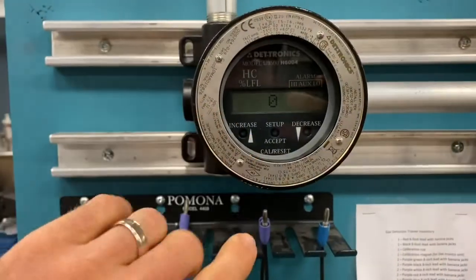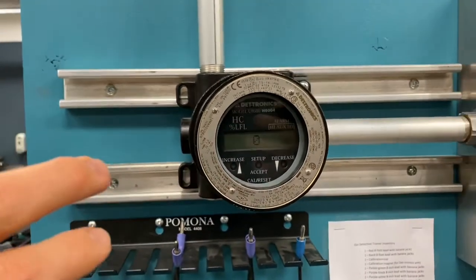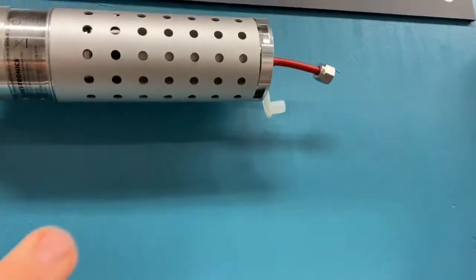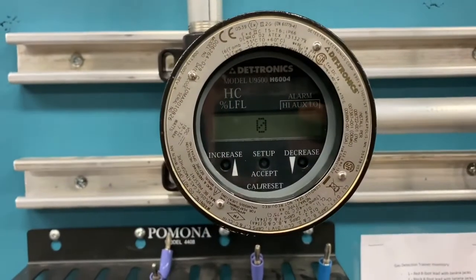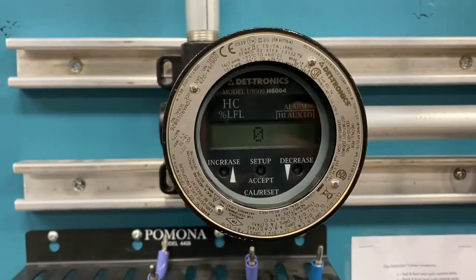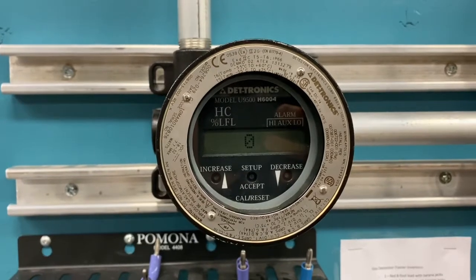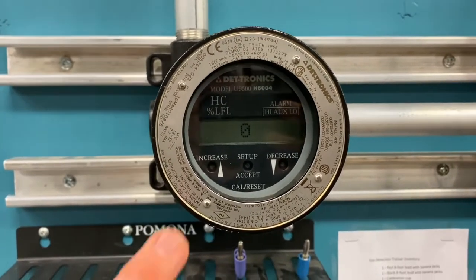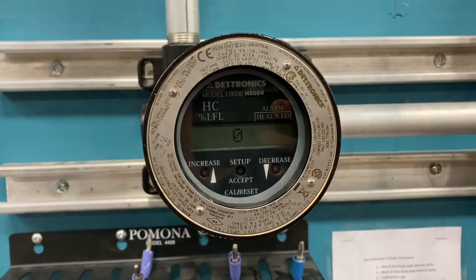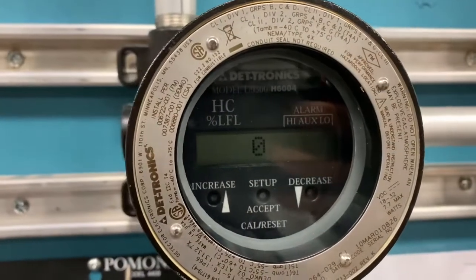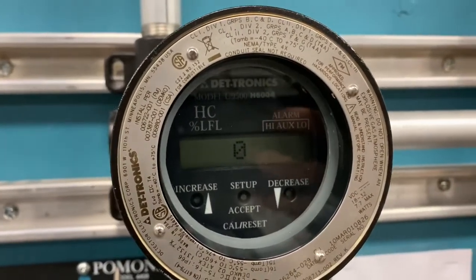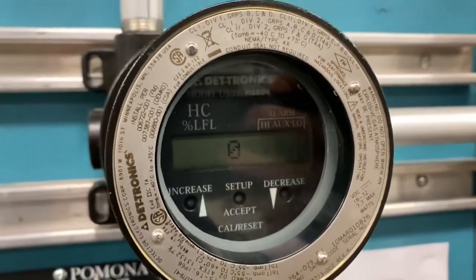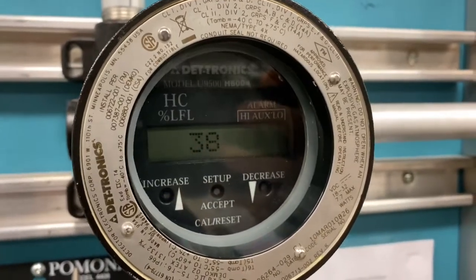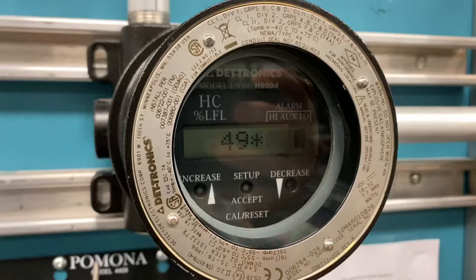Now that the sensor's had plenty of warm-up time, you can see it's at 0. I'm going to go ahead and introduce calibration gas up here, and we're going to see if there's any calibration drift with this sensor. So I'll introduce that 2.5% methane right now, and we'll see. This should come up to 50% LFL or LEL. All right, so I'm just about to turn on the calibration gas. I just wanted to catch to see how fast this transmitter reacts. And just checking to make sure the flow rate is correct.